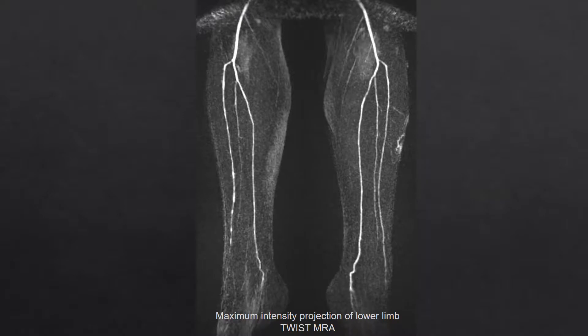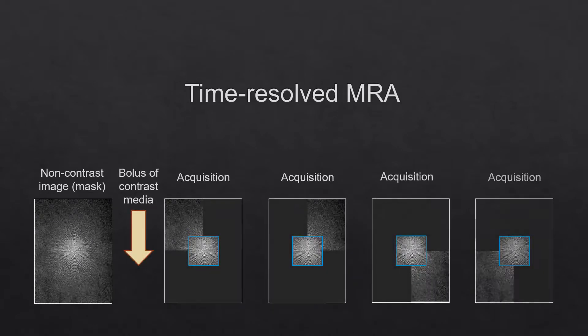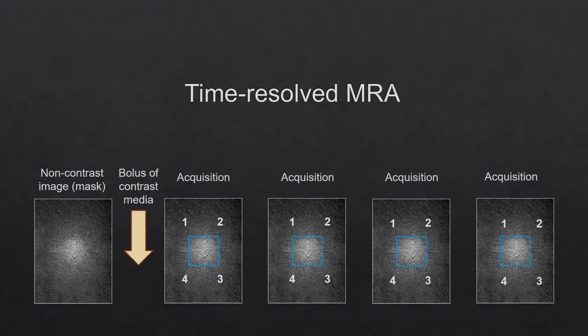Time-resolved MRA is a spoiled gradient echo sequence that uses multiple acceleration techniques including view-sharing. View-sharing involves filling the center of k-space over a short period of time and under-filling the rest. The missing data from the periphery of k-space is filled from the time points at either side to gather enough data to reconstruct a full image. The center of k-space is filled during each acquisition, while the periphery is partially filled and then stitched together to create the full image.